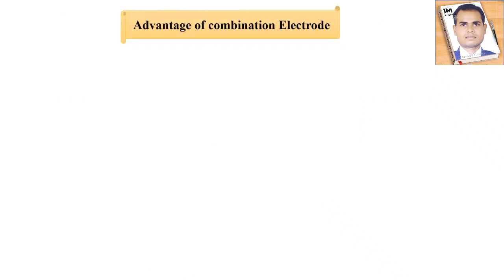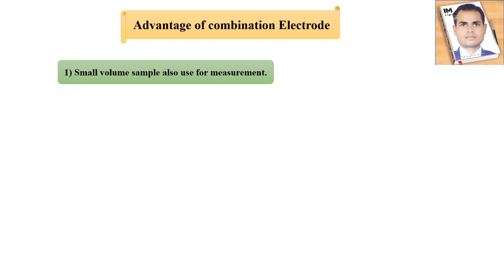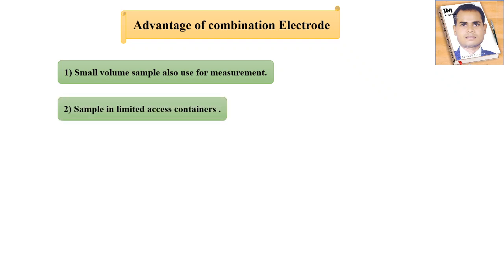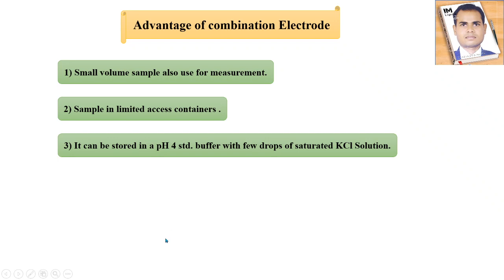Now we have to see the advantages of the combination electrode. The first advantage is that a small volume sample can also be used for measurements — if we have a very small amount of sample and need to analyze the hydrogen ion concentration, we can use the combination electrode. The next advantage is that it can be used with samples in limited access containers. Also, it can be stored in pH 4 standard buffer with a few drops of saturated KCl solution.